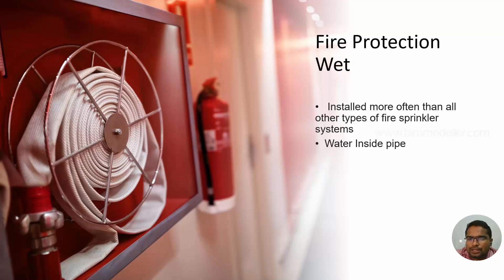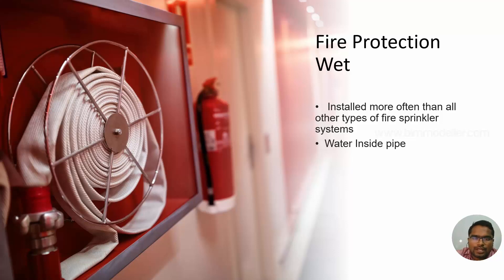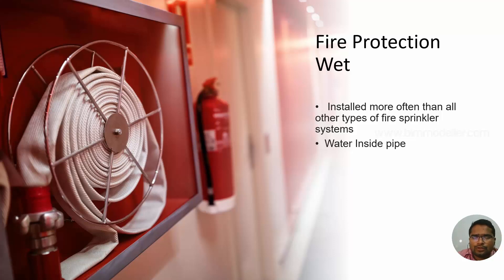Fire protection wet is the system installed most often — you will be seeing it more frequently. In a wet sprinkler system, the pipes have pressurized water in them at all times. Once a sprinkler blasts, the water will extinguish the fires. The problem is that water is present all the time, so if accidentally damaged, a sprinkler can cause damage to property — economic loss involving artwork, bookshelves, computers, and other things.